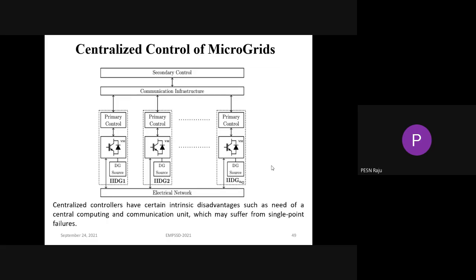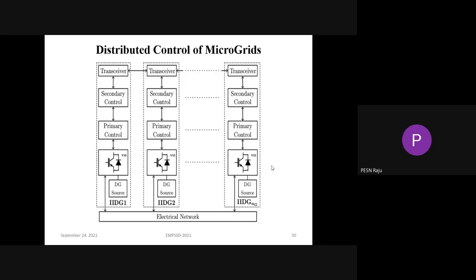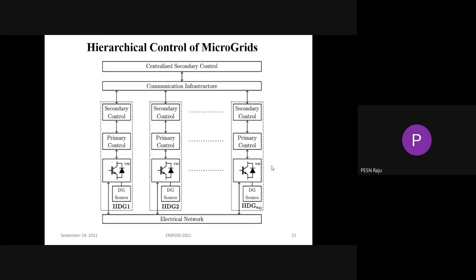Once the communication infrastructure has failed, there won't be any communication between the secondary level control loop and the primary level control loop. So as you can see, we have some advantages and drawbacks with the decentralized control loop, and some advantages and drawbacks with the centralized control loop. By combining decentralized and centralized, we can have more advantages and reduce those drawbacks. This is called the hierarchical level control loop. Every DG will have its own secondary level control loop, and we will have a centralized secondary level control loop, with the communication infrastructure between that centralized secondary level control loop and the decentralized secondary level control loops. Even if there is a failure of the communication infrastructure, the secondary level control loop above the primary level control loop will still take the actions, and it will provide the minimum stability of the microgrid.